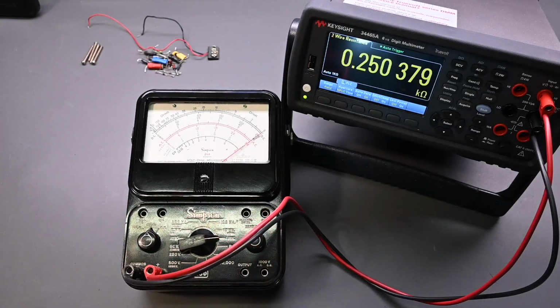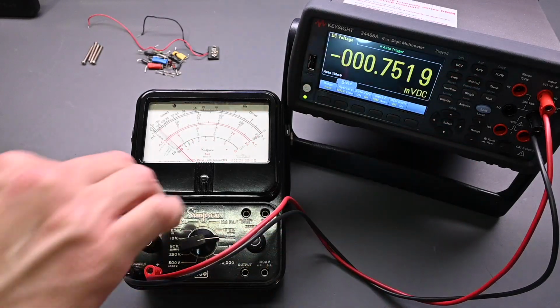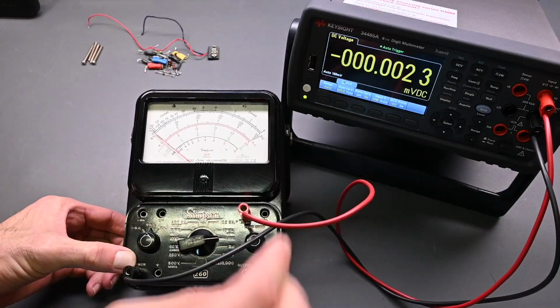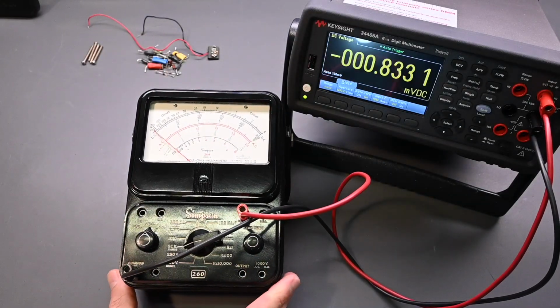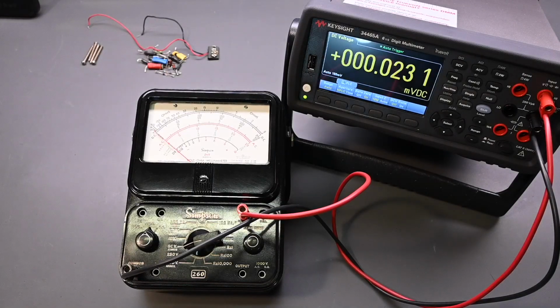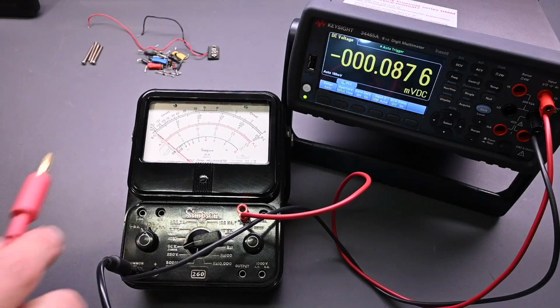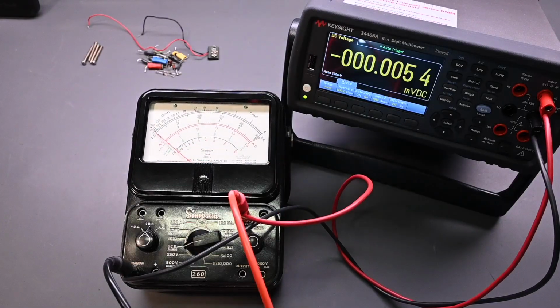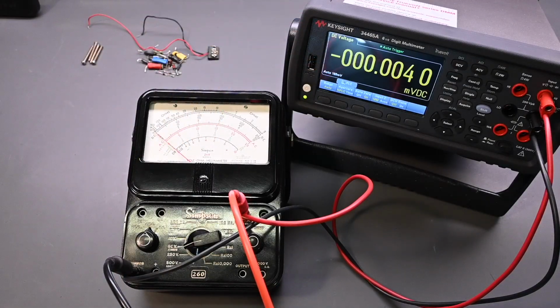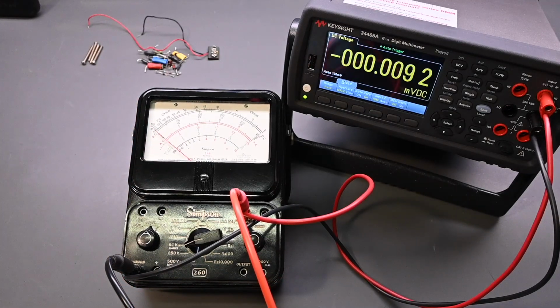All right, so let's put some voltage to the meter and see how it actually measures. So what I'm going to do here is just put this back to DC volts, and I'll move this over here to this range, all the way around here like that. And I'm going to grab these test leads. So I'm going to use this power supply, the Keithley 236, and go over here. Keithley is turned off right now. So we'll just use the Keysight digital multimeter to make the comparison. We'll just measure the voltage and see that this is reading reasonably close. And turn this Keithley 236 on. And it is set for 0.25 volts right now.